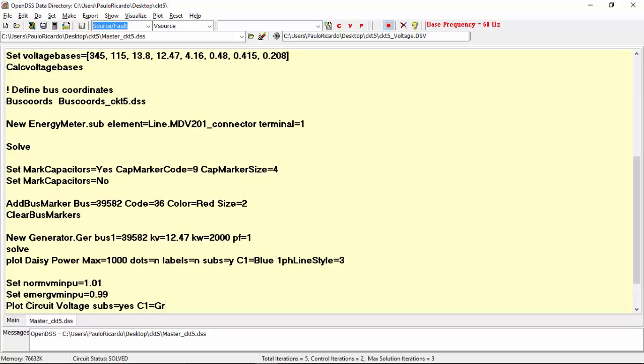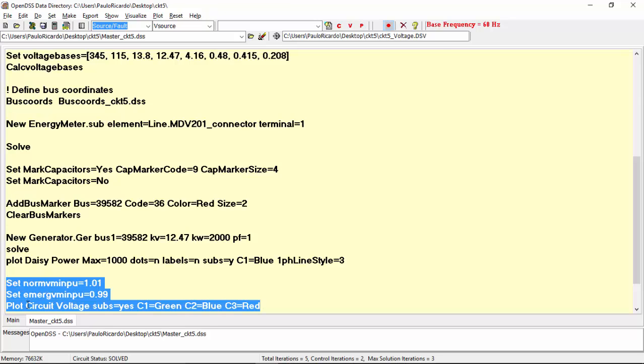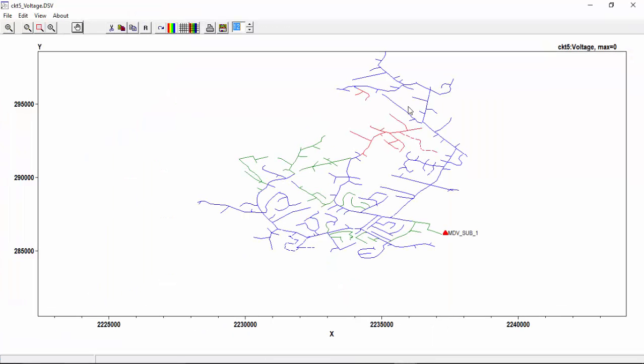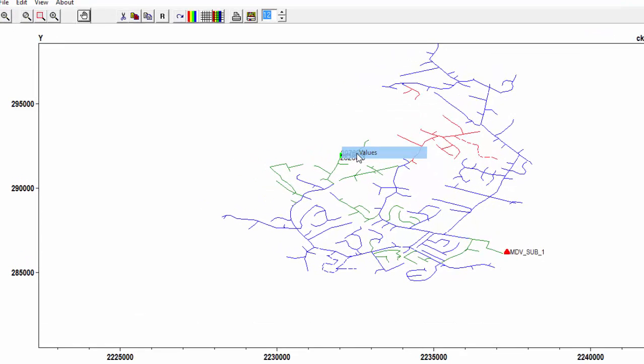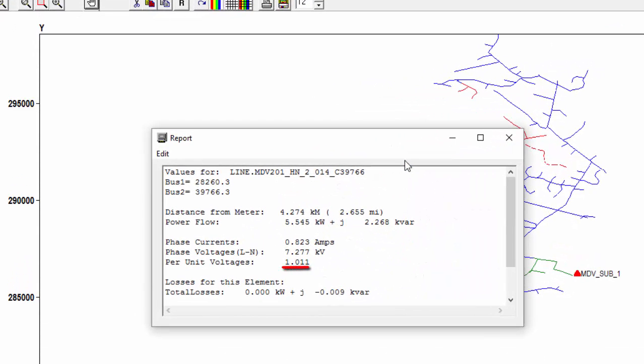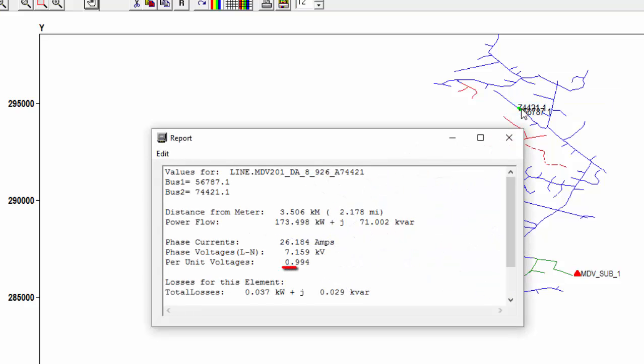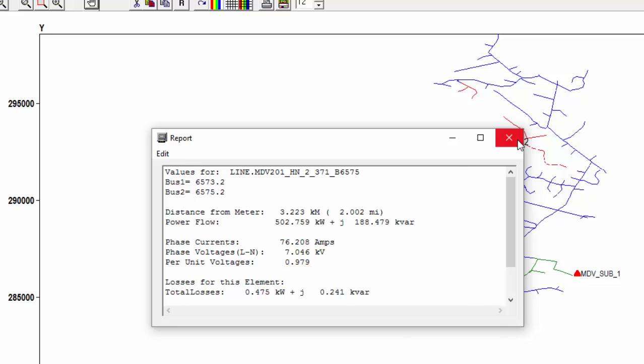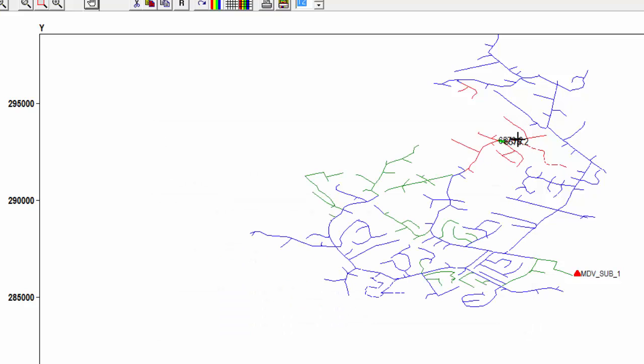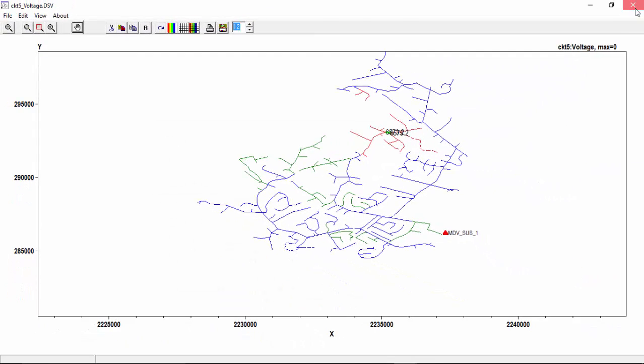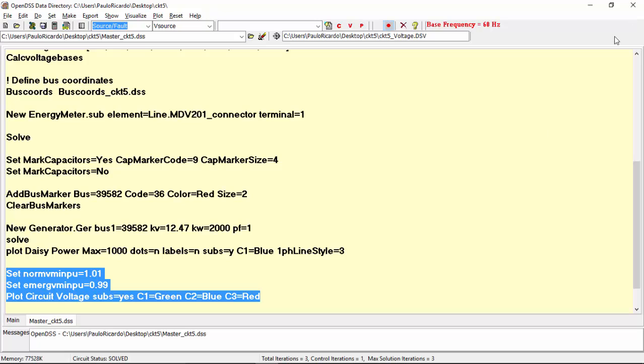I will choose the colors green, blue and red. As you can see, there are three voltage levels depicted in this plot. If the voltage in an area of the circuit plot is higher than norm vminpu, the circuit will be plotted according to color c1, that is green in this case. If the voltage is between norm vminpu and emerge vminpu, the circuit is plotted according to color c2, blue. And finally, if the voltage is below emerge vminpu, the circuit is plotted according to color c3, red. So, these two parameters define three voltage levels.